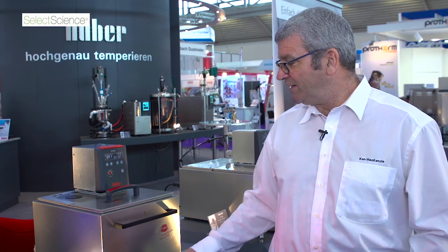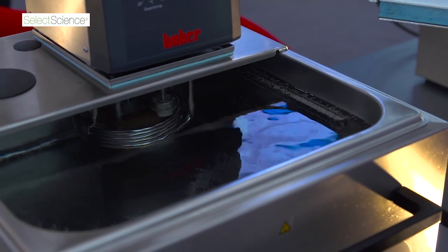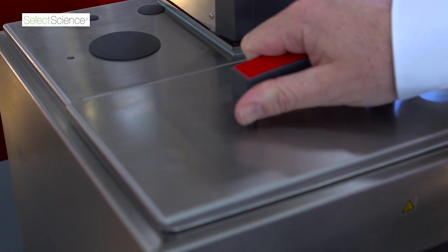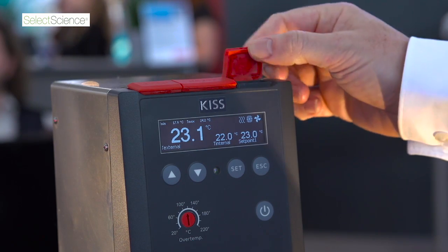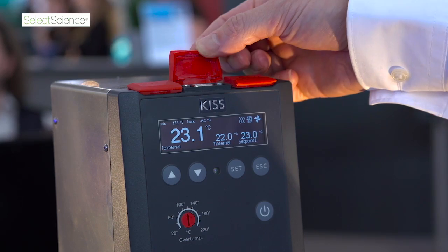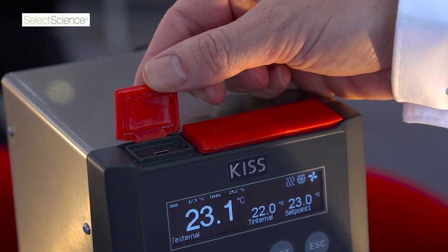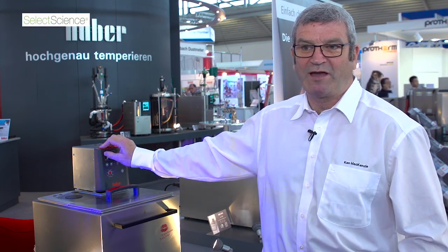The features of the unit — we don't compromise on materials. They're all made of stainless steel construction, so the lifetime is a long time. We have red, blue and black, and at the top here we can see these covers protecting the interfaces: the process-based PT100, RS232 interface, and the USB device port. So it's easy to communicate with both for using and also for running diagnostic files when it comes time for a service.